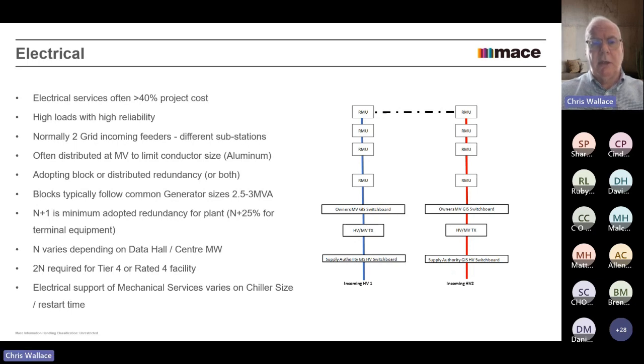Often, because of the size and to try and keep the conductor sizes down, they will distribute around the building at medium voltage. Depending on the size, as a rule of thumb, most data centers are below 30 megawatts, or 30 MVA, because with a data center power load, the power factor is almost always unity or close to unity. So megawatts and MVA become almost the same.